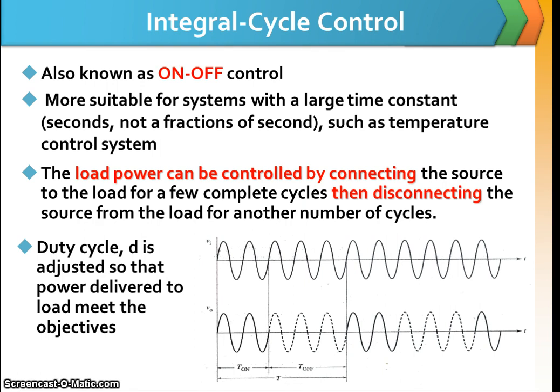As I mentioned earlier, integral switching schemes for AC to AC have two types. Number one, integral cycle control. And number two, called phase control. Integral cycle control also known as on-off control, which is suitable for systems with a large time constant, such as temperature control systems.